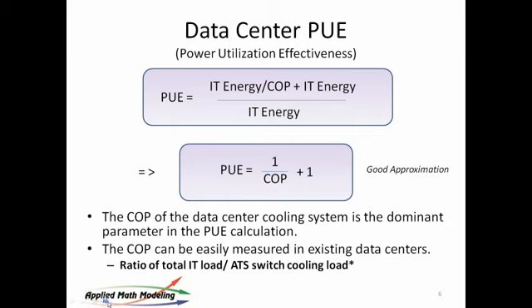And the way to really get your hands around it is to measure the amount of energy that's being consumed by your cooling system and compare it to the energy being consumed by your IT equipment. Just compare them. The energy being consumed by your IT equipment is easy to see because you've got a backup system, a diesel generator or something, batteries standing by, and you most likely have a meter on that looking at the amount of energy being consumed, because that's, of course, what you need the generator to be able to handle.